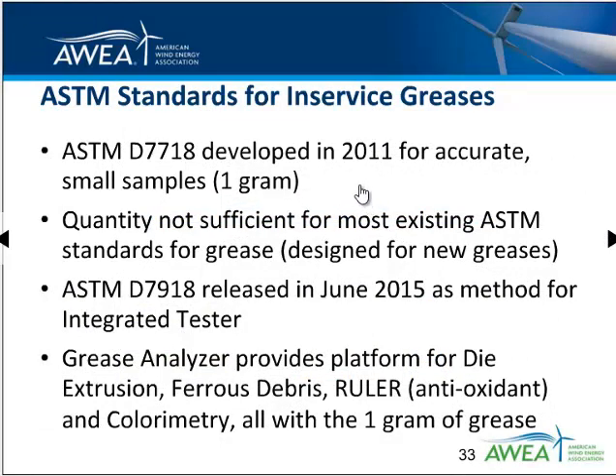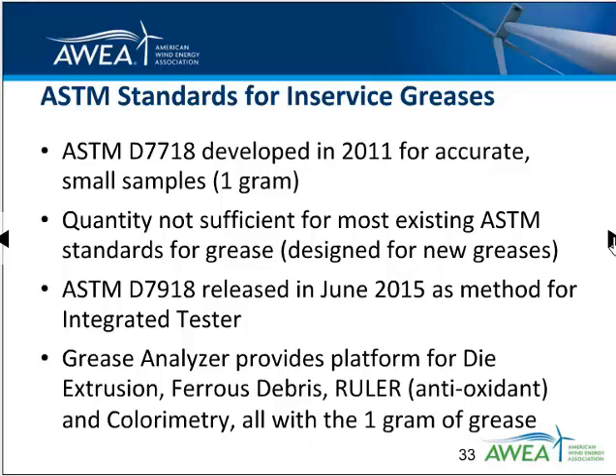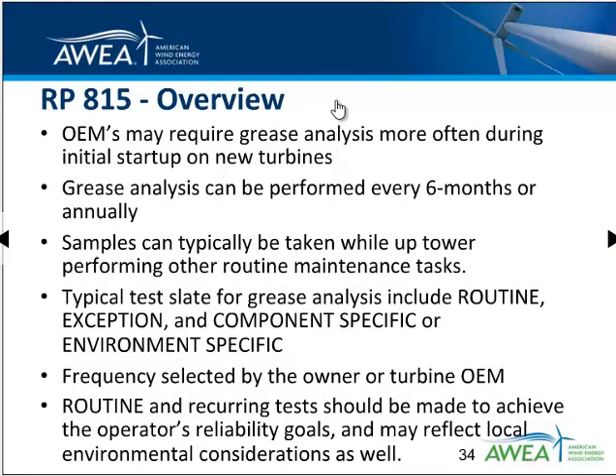The ASTM standards for in-service greases include D7718, developed in 2011 for taking small samples of about one gram. That quantity is not sufficient for most previously existing ASTM standards for grease, which were designed for new greases and batch testing. Earlier this year, ASTM released D7918, a method using an integrated tester. With the samplers outlined in D7718 and the analysis process in D7918, there's a method to take consistent one-gram samples and perform a number of tests, including ferrous debris levels, antioxidant levels, color variation — which can tell us the right grease is being used, if it's aging or contaminating — all with one gram of grease.